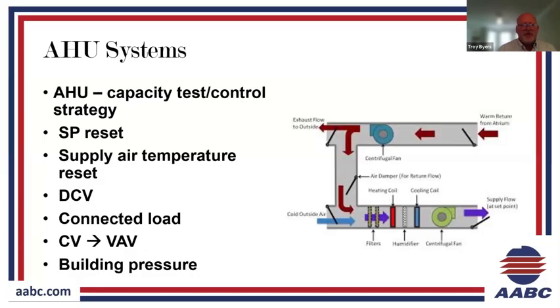Another strategy would involve temperature reset of the supply air temperature. Supply air temperature reset recognizes that we've met our load in the space, and so we can start letting the temperature of the discharge air increase. And so now, if say it was a chilled water system, we're using less chilled water to maintain that low discharge air temp. And we're also using less reheat, whether that's electric or hydronic, to maintain space conditions. So obviously you have to be careful with humidity control. If you raise that supply air temperature, you're also allowing the relative humidity to increase there. So watching out for that.